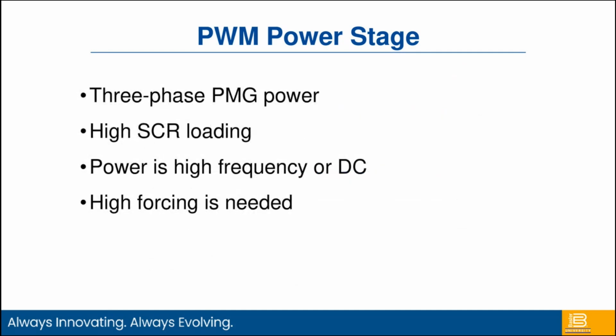The reasons why we use pulse width modulated power stages are many. There are some advantages to them. It allows us to use three-phase PMG power. One thing I didn't mention when we were talking about the SCR power stage is that those SCRs, because they have to know when to gate on and off, are tuned to the frequency of the power input. They may only be able to handle 50 or 60 hertz, or maybe they're set up to handle a 400 hertz PMG. So it may require a different power stage topology. Not that they can't be used in those applications, they're just not as flexible.